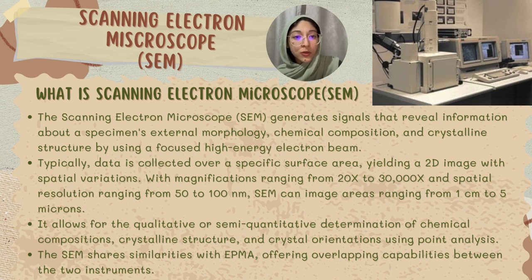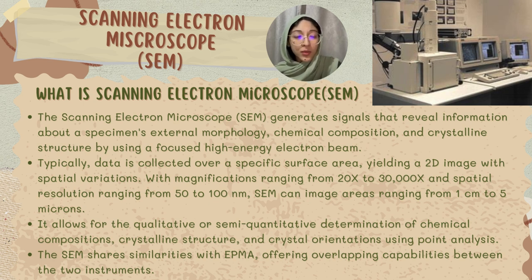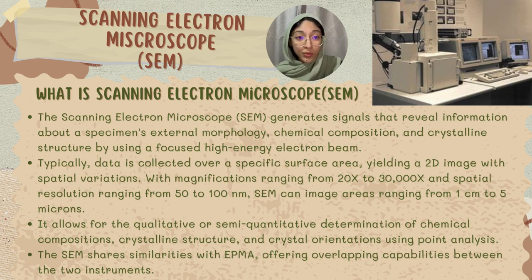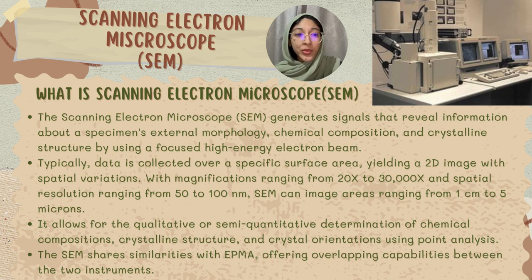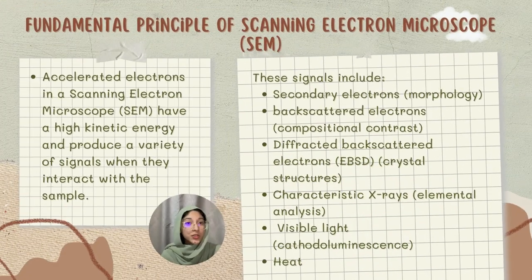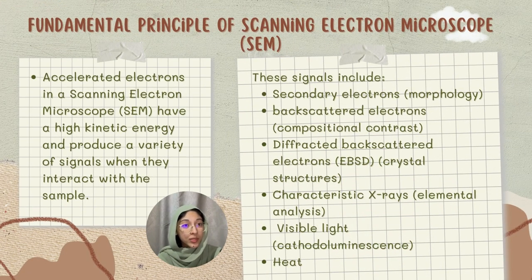With magnifications ranging from 20 to 30,000 times and spatial resolution ranging from 50 to 100 nanometers, SEM can image areas ranging from one centimeter to five microns. It allows for the qualitative or semi-quantitative determination of chemical compositions, crystal structure, and crystal orientation using point analysis. The SEM shares similarities with EPMA, offering overlapping capabilities between the two instruments.